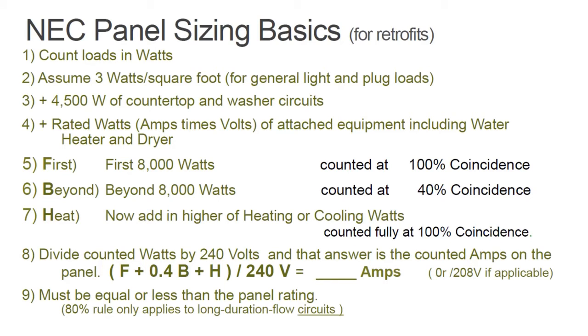Okay, now we've gone through steps 5, 6, and 7. Then the 8th one is, sum up those first 8,000 watts plus 40% of everything over that, plus the heating watts, divide it all by 240 volts. And that equals the number of amps of counted load that you have on the panel. For a 100 amp panel, that must be equal to or less than 100 amps. So it can be 99 amps and that clears, or 99.5 or 99.9. They all clear, and you can get permission to move forward with your existing panel in those cases.